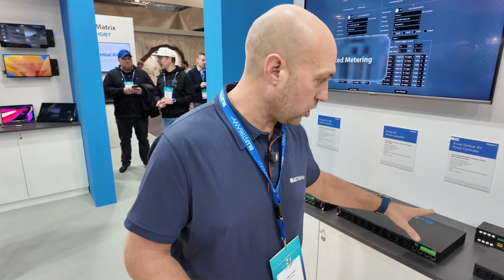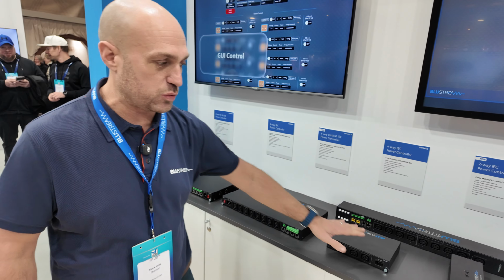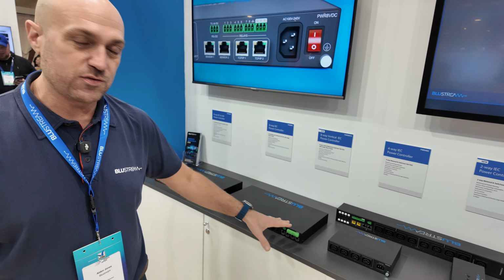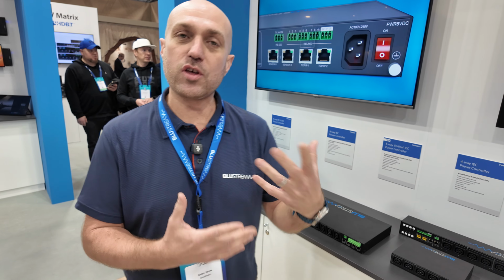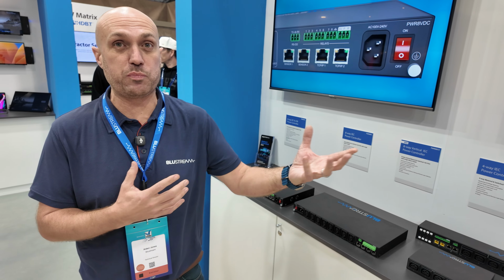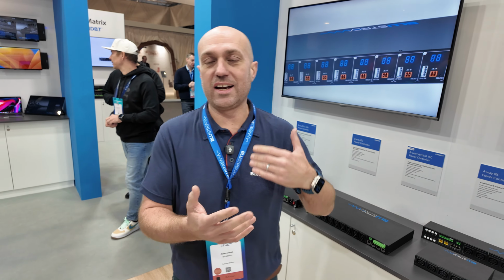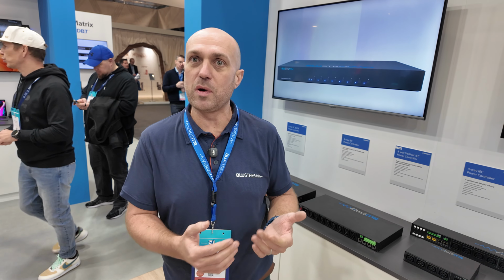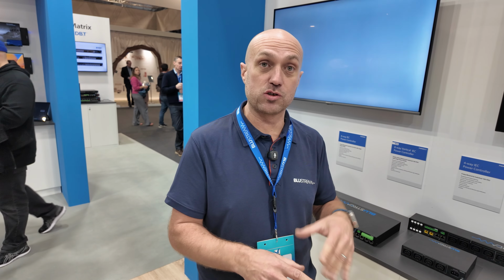There's sensor ports on the 8-way variations, but not on the smaller ones. This gives you the ability to do movement, humidity, temperature - those types of sensors, integration with building management systems. If the temperature in a rack room becomes too much, let's turn off certain things or turn on certain things to help with the cooling effect.